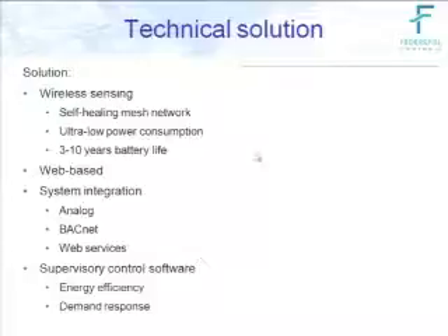We also communicate with building management systems or building automation systems in your data centers. BACnet is an open protocol used to talk to BMSs, and we can communicate with them to control set points and cooling units. Typically, more sophisticated customers already have their cooling units networked together, and we just pass through their system so they can use the same interface and do manual overrides of our control if they desire.